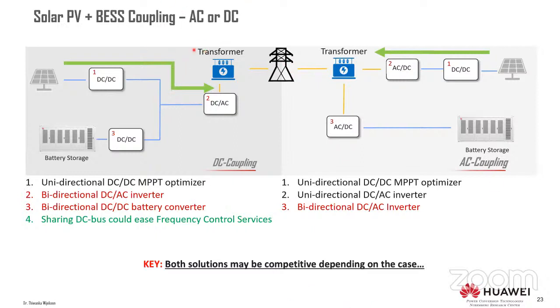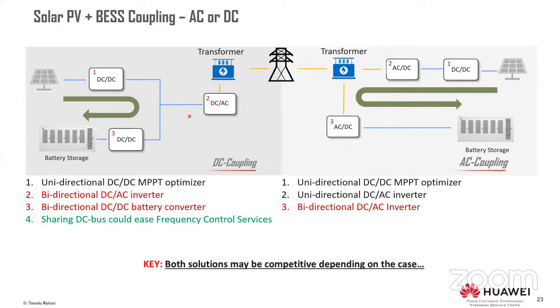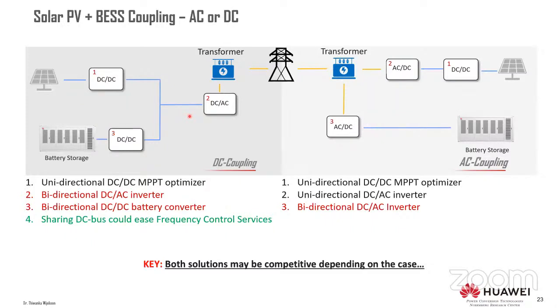Whereas in the DC coupled system, after the DC-DC converter you couple through another DC to DC converter, and then you reuse the inverter for both feeding energy to the grid generated from photovoltaic, as well as energy generated when the PV is not there. If you want to feed battery power to the grid, you reuse your inverter.